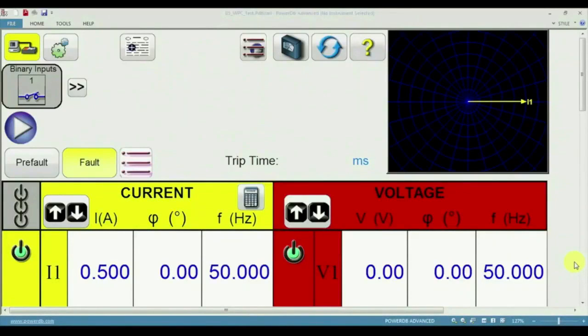In this video, we are going to test wrong phase coupling, WPC. So let's see how to simulate this. We have to connect the feedback to the WPC contact. As per the specification, the WPC is an impedance test which is configured between 90 to 150 degree, that is in the second quadrant. So the distance protection is a quadrilateral characteristics in all the four quadrants, whereas WPC lies only in the second quadrant between 90 to 150. So in order to compensate the regenerative braking, this angle is kept as 150 degree. The impedance reach value also varies from 60 ohms at the upper limit and 2 ohms in the lower limit.